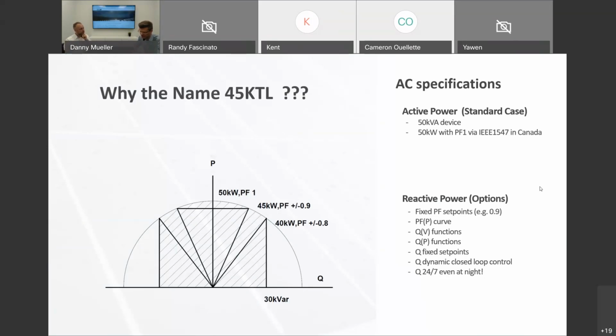Most other jurisdictions, for example, in Europe or in California under Rule 21, already require some smart inverter features to support the grid, and they require full nameplate output power at a power factor of 0.9. And if you have 50 kVA available at 0.9 power factor, in these markets, you only get 45 kW out of the product. And that's why the product is called a 45 KTL. Since most manufacturers are not specifically developing a product for a very small Canadian market, we are, of course, piggybacking on the US market, and there the market name 45 KTL represents more accurately what the system can actually do.